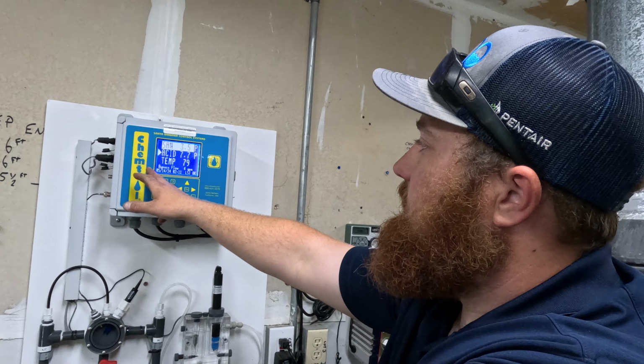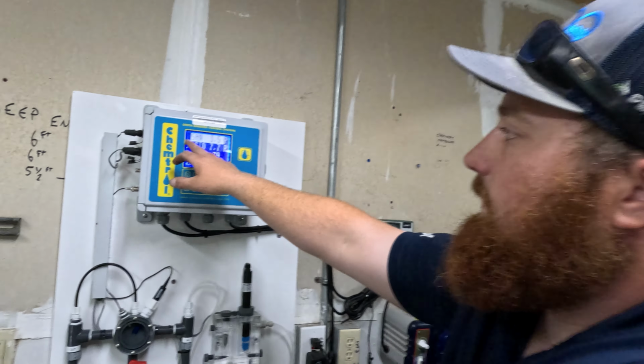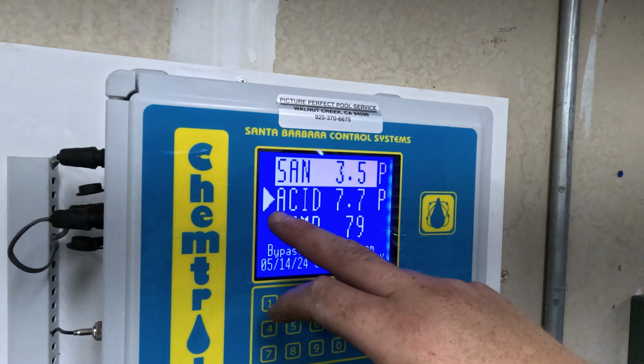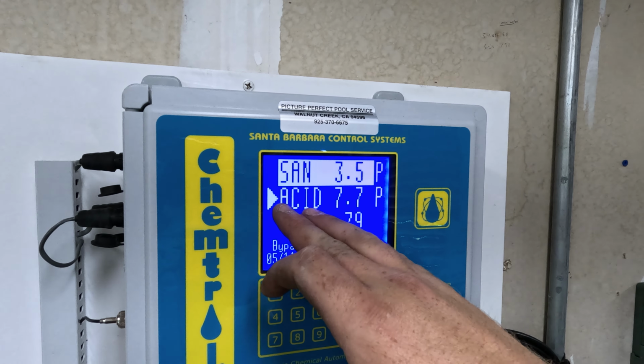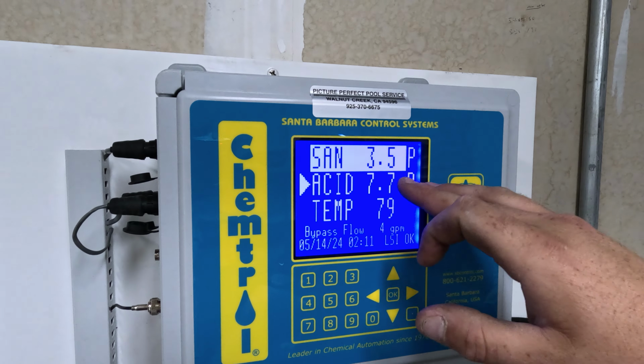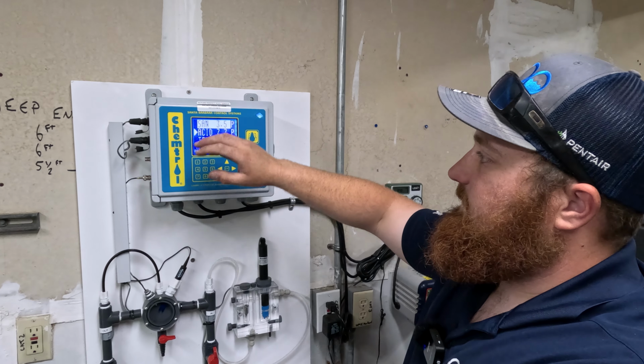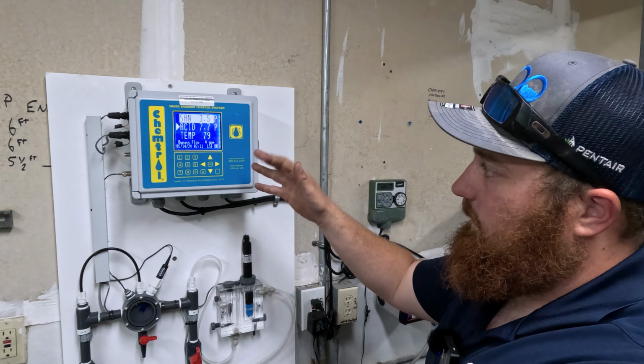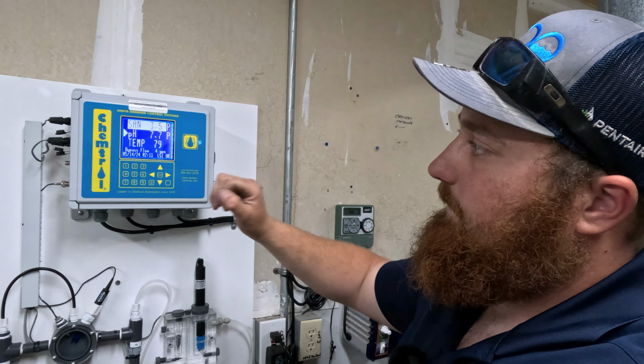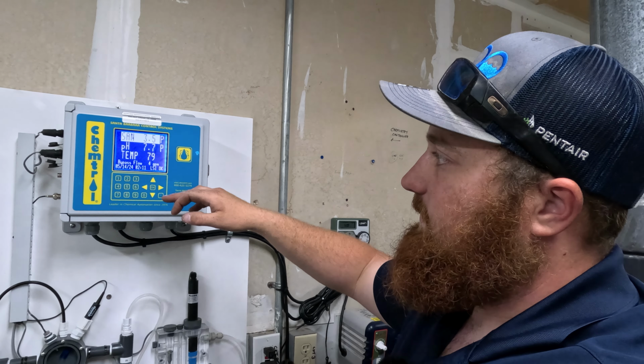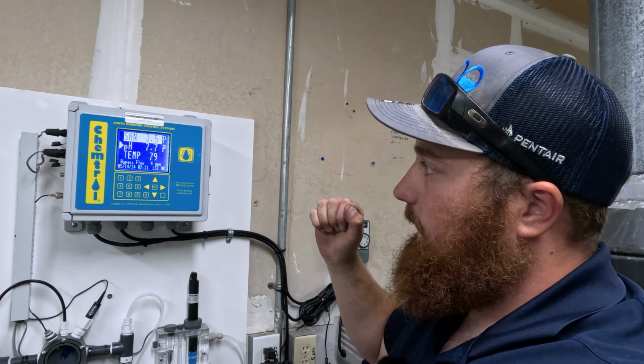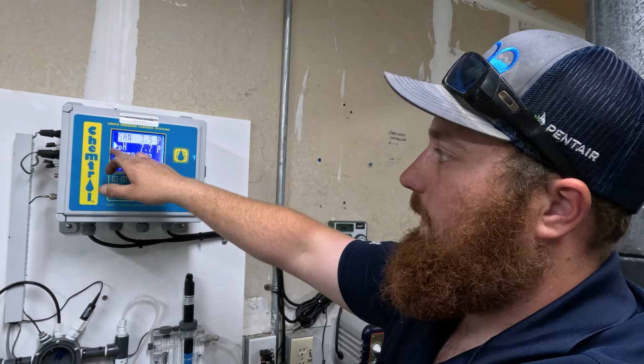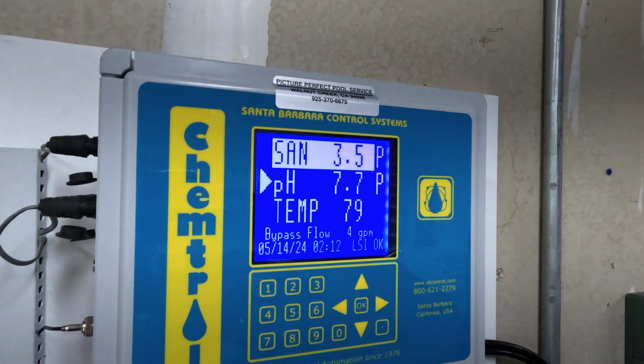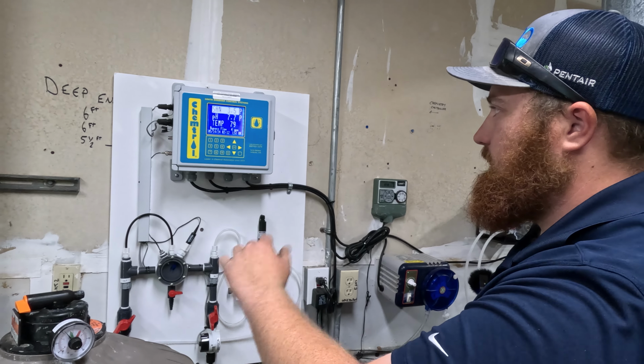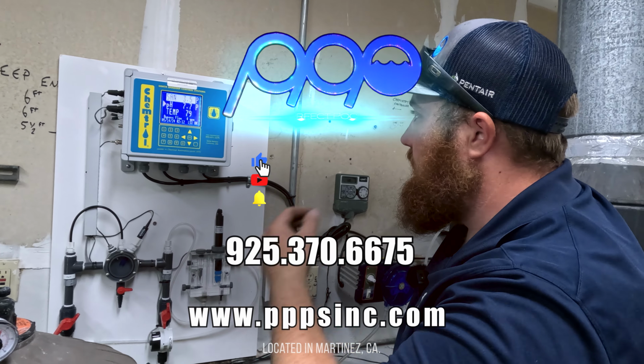When you're looking at the main screen and it's feeding, you're going to have this little arrow next to the feed. What that means is, in solid form like this, it's feeding continuously to lower your pH down to 7.5. When it's flashing, that's when it's in that progressive zone and doing the pulse feeding. So when it's flashing, it's letting you know, hey, we're trying to get it down to 7.5, but we turned off the pump to make sure we don't overfeed. Then a few moments later, it's going to go back to a solid arrow, and that's when it's actually feeding. So those are just some of the key points to the Chemtrol 1555. Nice. Yeah, we'll go back and make sure. See, 600.